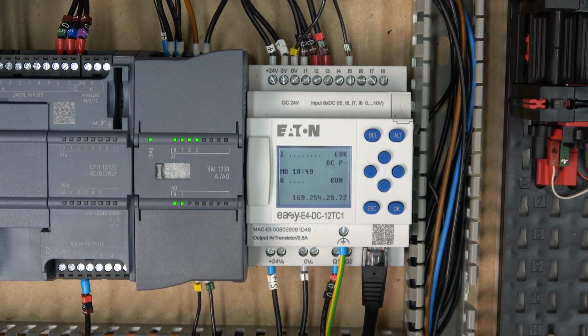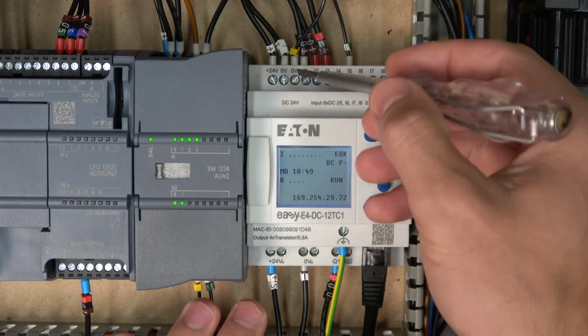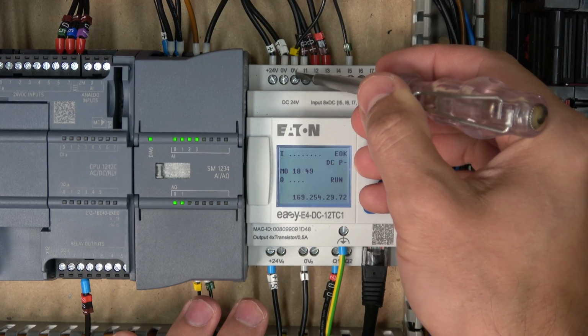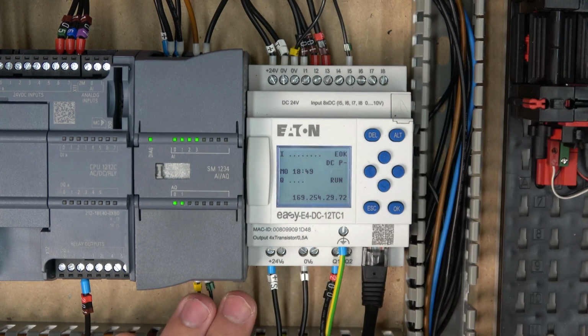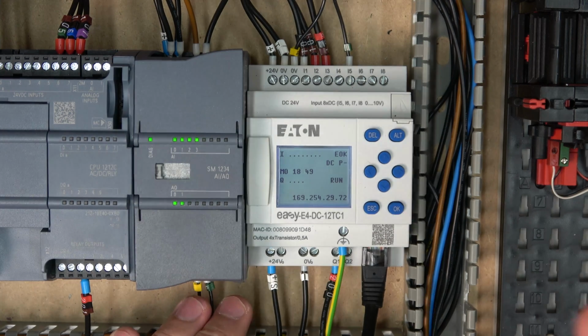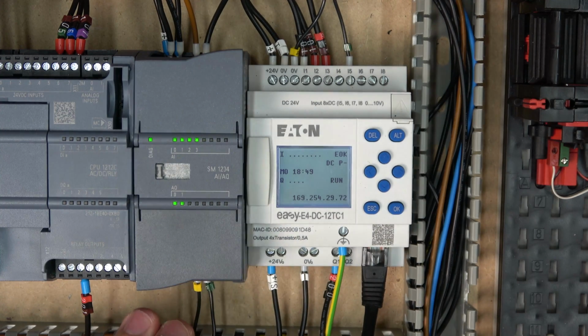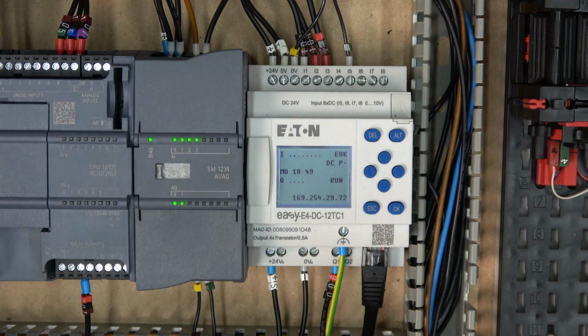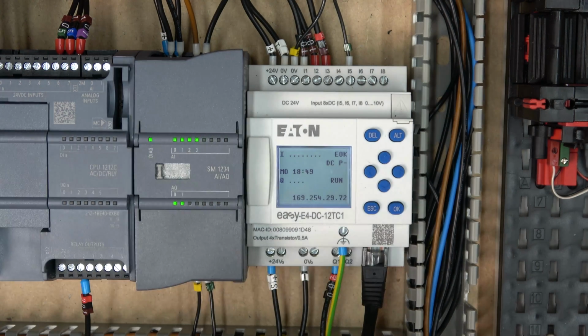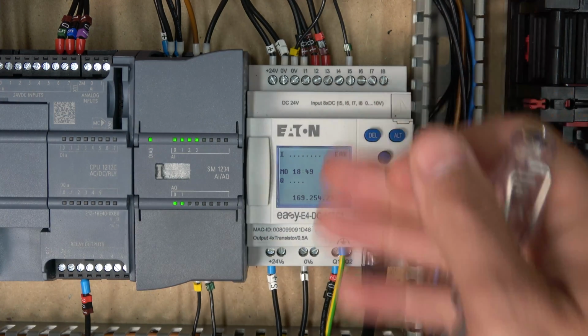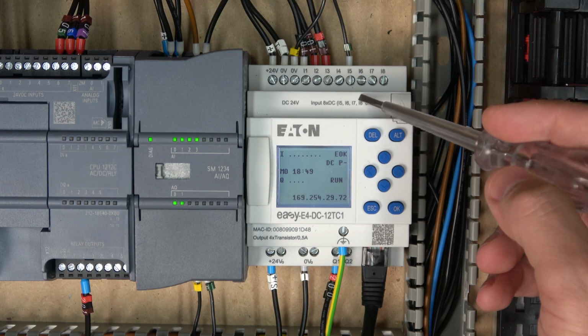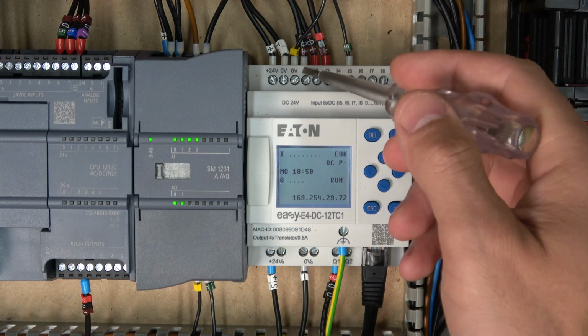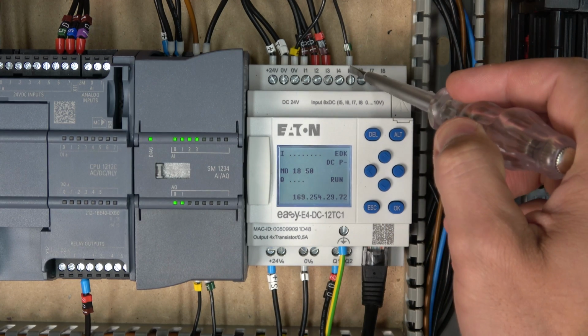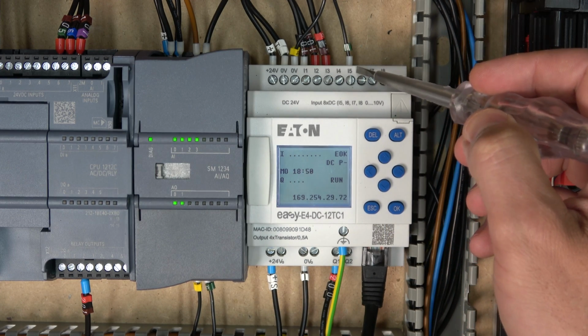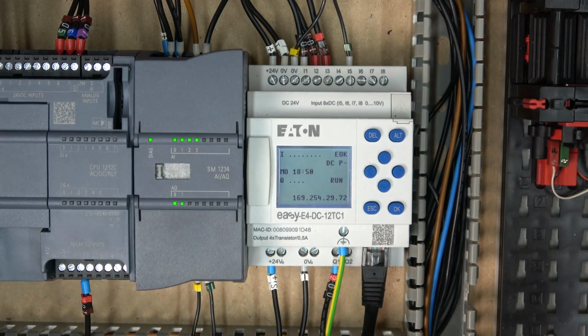The wiring is very simple. You use the second zero right here. That would be your zero point, which is going to be coming from your transmitter, whichever you are using, or a pressure sensor. There's many. Any type of sensor that produces 0 to 10 volts can send that information back to your controller to these channels, I5, 6, 7, and 8. So zero goes to here, and the plus side goes to I5, and that's it, the wiring is pretty much done.